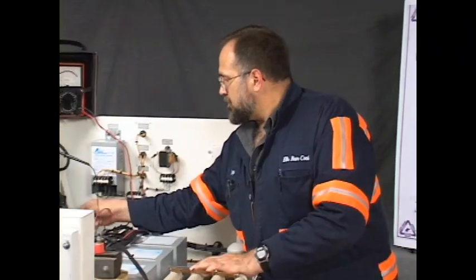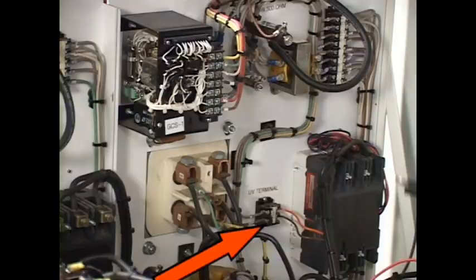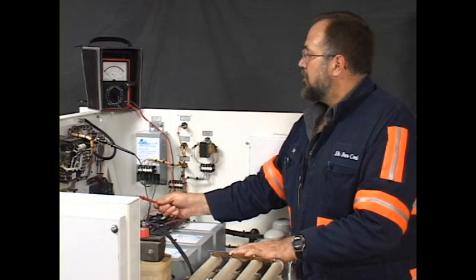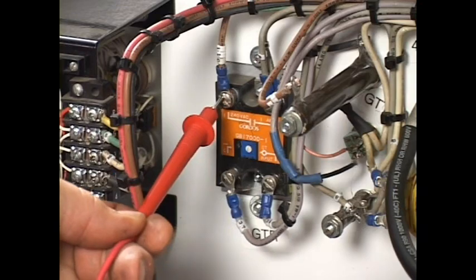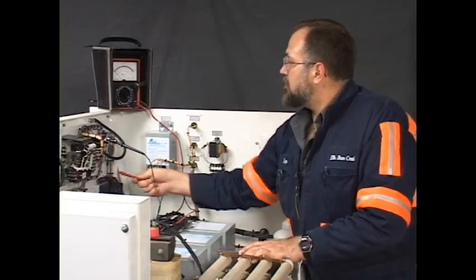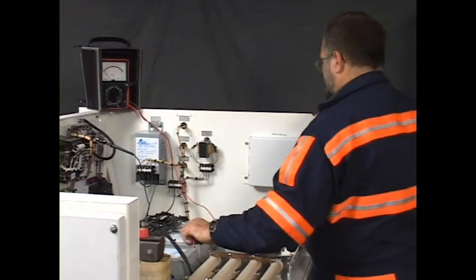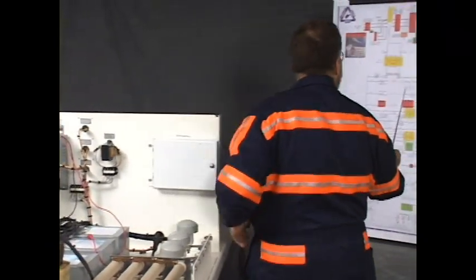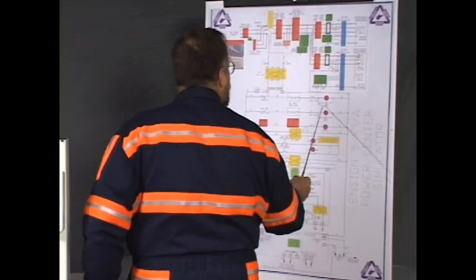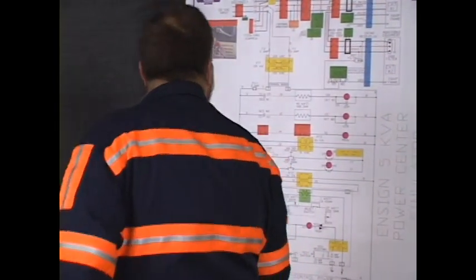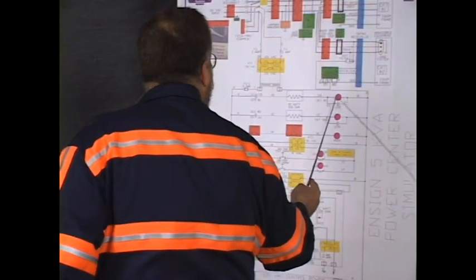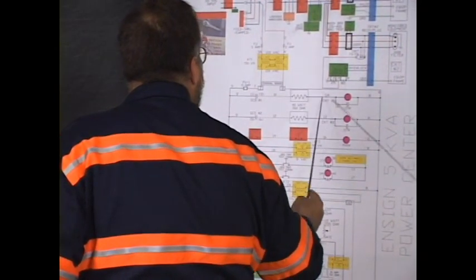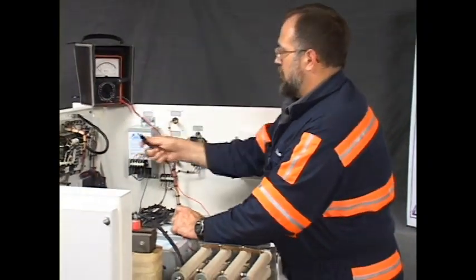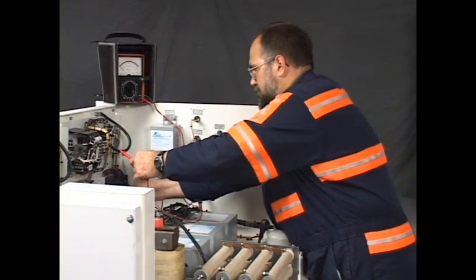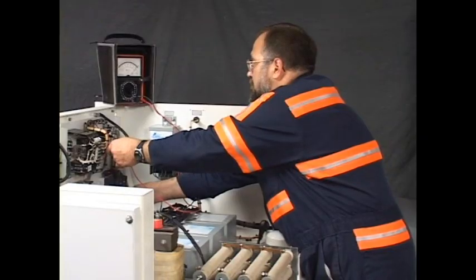And the first place I'm going to check is wire 11 on the UVR. It reads open. Wow. Let's check it to 11 on the GTR. Still reads open. We're reading an open circuit between here and this point and this point. Just to further pinpoint that a bit, let's read from the UVR to the GTR, and that will tell us if it's that wire. And we have a circuit there.